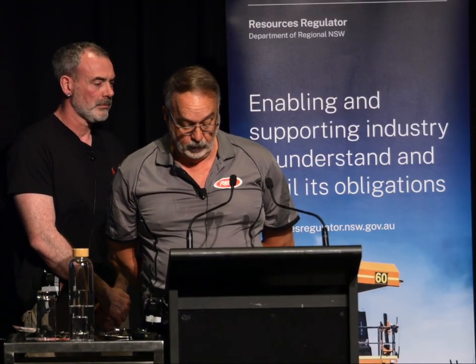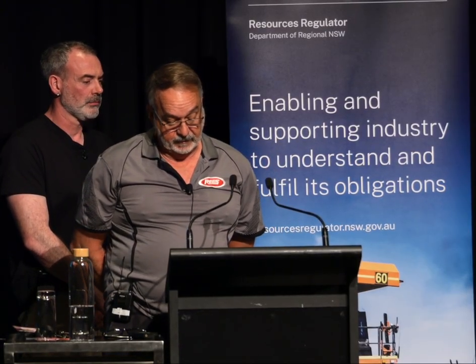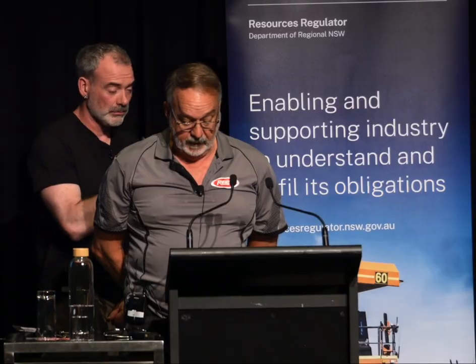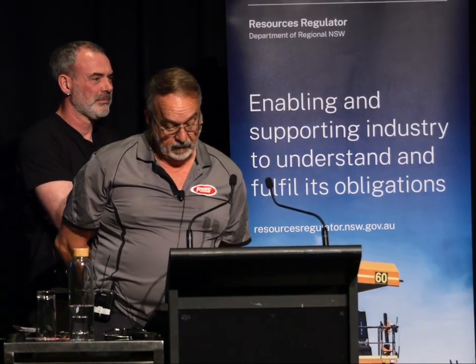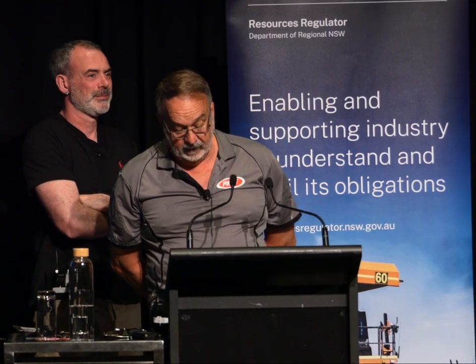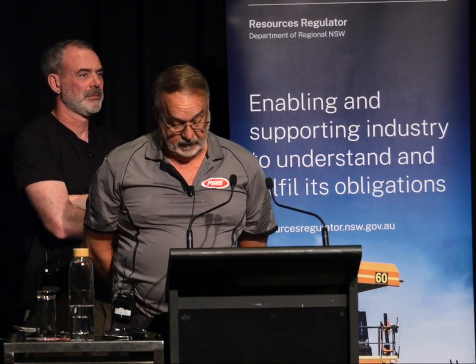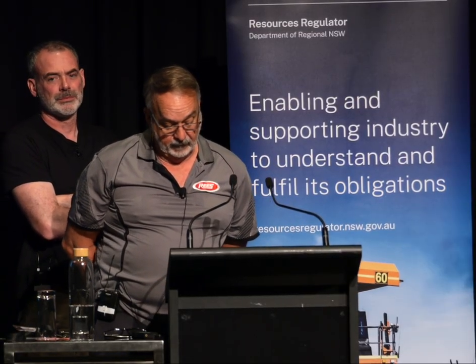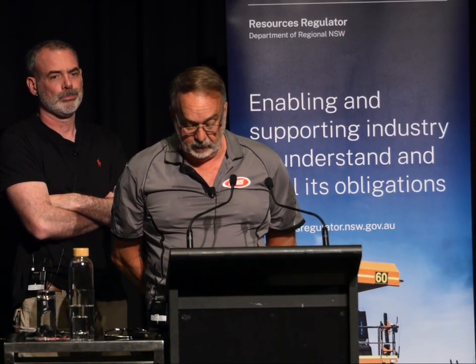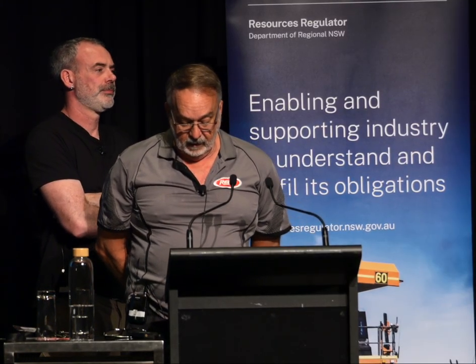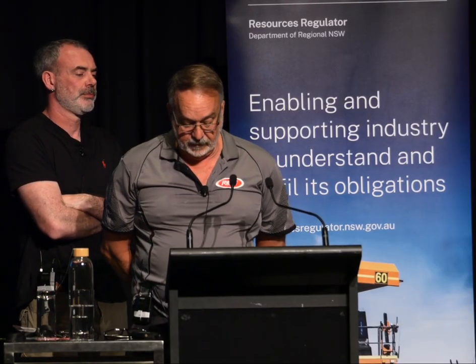15 would be to take oil samples. 16 would be to energise the unit with no load, then wait 3 hours prior to adding a load, and then connect the load. 17 would be, the next day, to check the temperature and the pressures. 18 would be to follow maintenance schedules and procedures. And the last one would be to periodically monitor and record tank pressures and confirm tank seals.